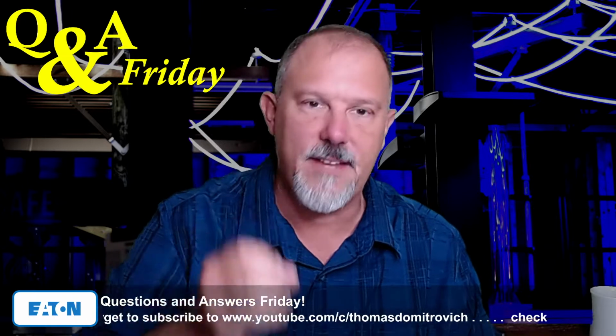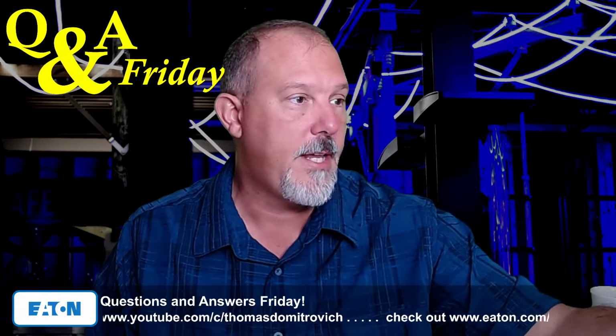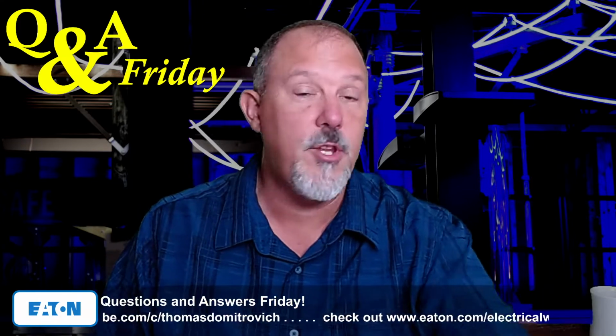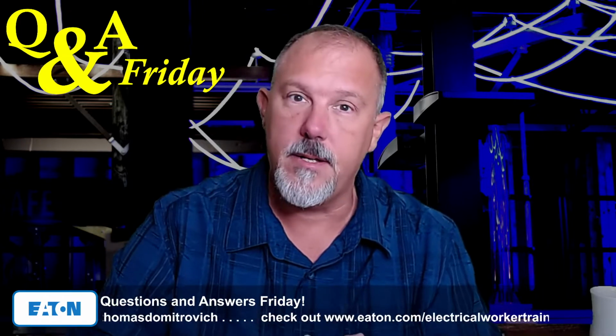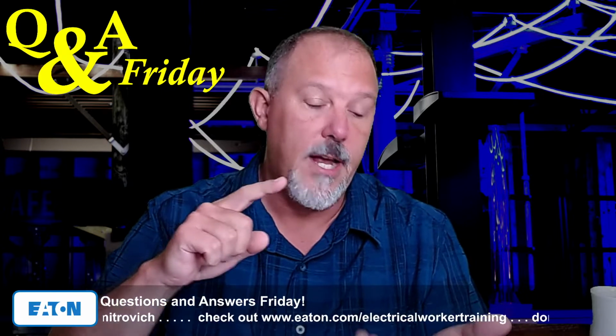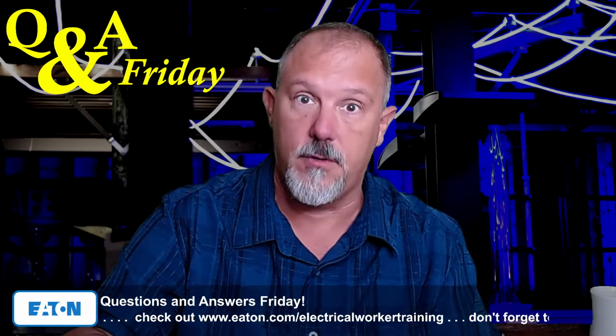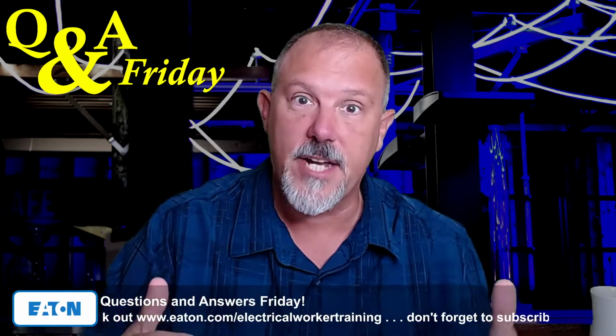It's an electrically safe work condition. Because to your point, you're saying that you have to ground it. Yeah, but you have to lock and tag it out. You've got to test for absence of voltage. And the test for absence of voltage is energized work.